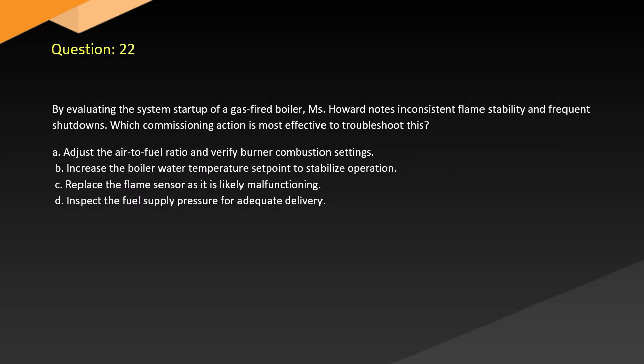Question 22. By evaluating the system startup of a gas-fired boiler, Hal notes inconsistent flame stability and frequent shutdowns. Which commissioning action is most effective to troubleshoot this? A. Adjust the air-to-fuel ratio and verify burner combustion settings. B. Increase the boiler water temperature set point to stabilize operation. C. Replace the flame sensor as it is likely malfunctioning. D. Inspect the fuel supply pressure for adequate delivery.